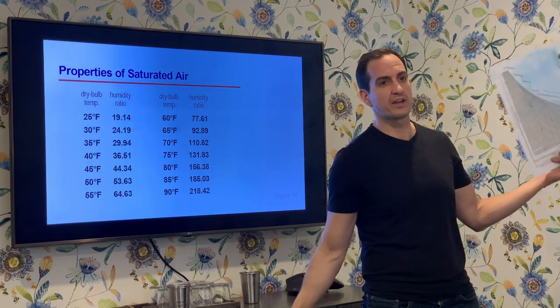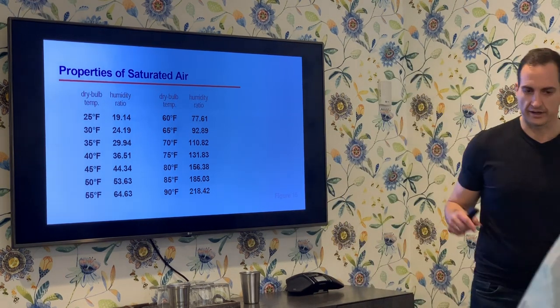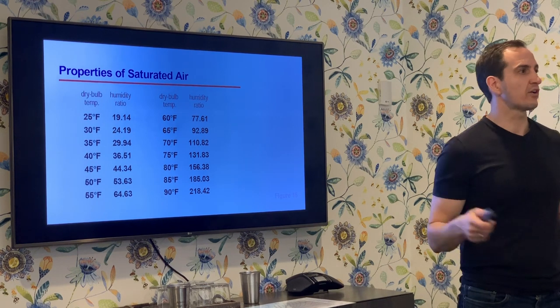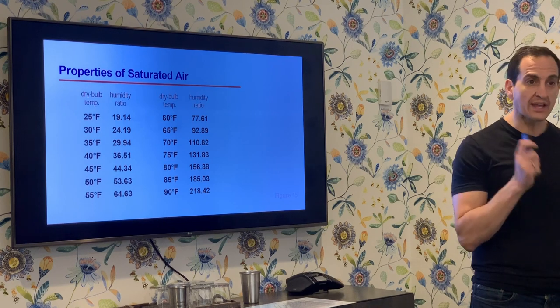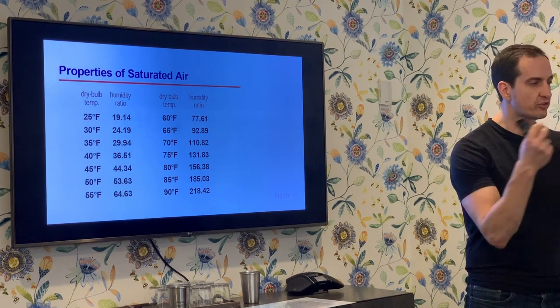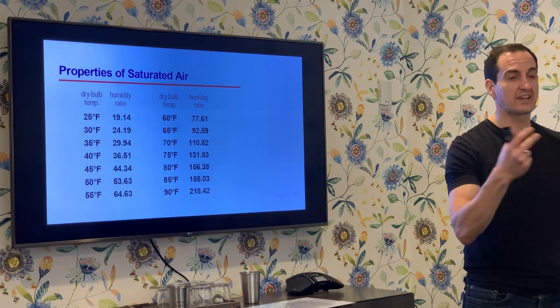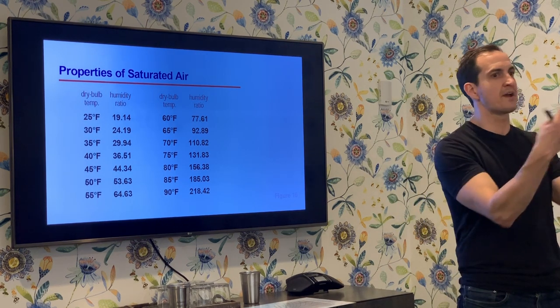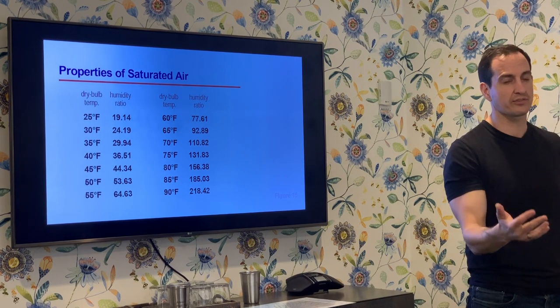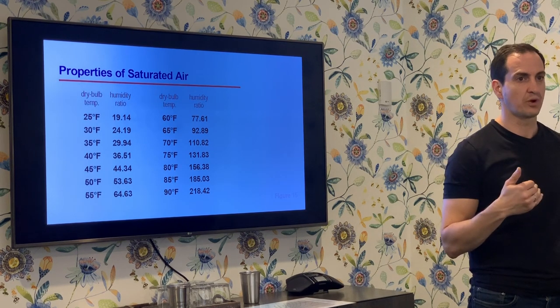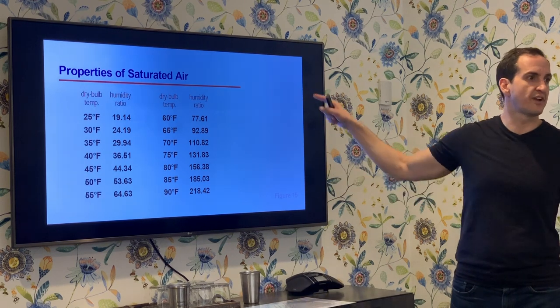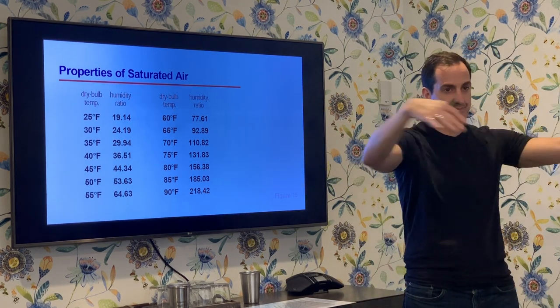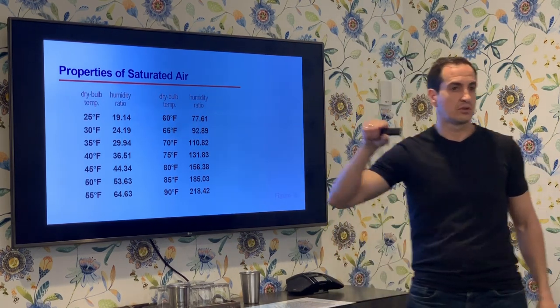Where did this chart come from? One of the places you can start is by making saturated air — you can spray moisture into the air and come up with a saturated condition at almost any temperature. Spray water inside a box and slowly heat it up to whatever temperature you want to measure, then look at the amount of water inside that box. They did this for a number of different temperatures and came up with a humidity ratio: for every pound of air at fully saturated conditions at 40°F, you get 19.4 grains per pound of moisture.